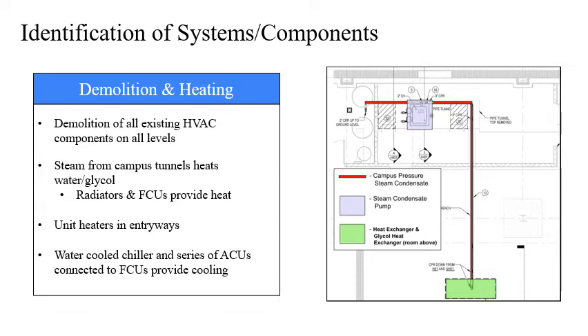For air temperature regulation, the heating system uses pressurized steam from the campus steam tunnels to pass through a condensate return pump in the tunnel level, then move up into a heat exchanger and a glycol heat exchanger on the ground level to heat water and glycol water mix, as shown here. A series of circulating pumps are then used to move the liquids to fin tube radiators and fan coil units throughout the building to provide heat. Other equipment used to regulate the liquids in this system include expansion tanks and air-dirt separators located on the ground floor. Unit heaters are also used, primarily in entrance vestibules and service corridors.